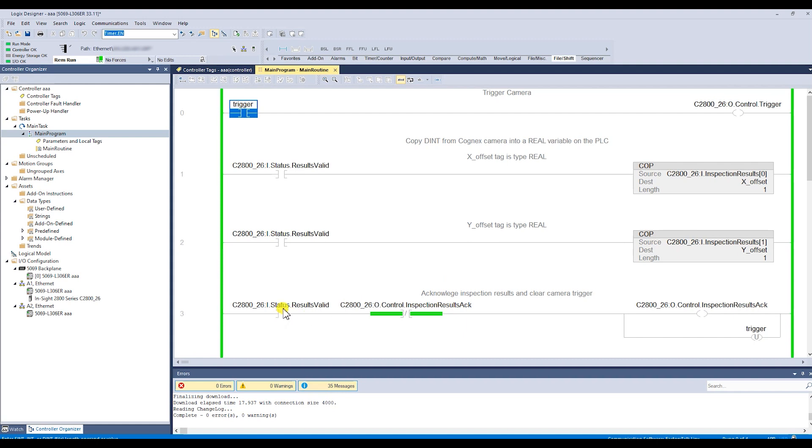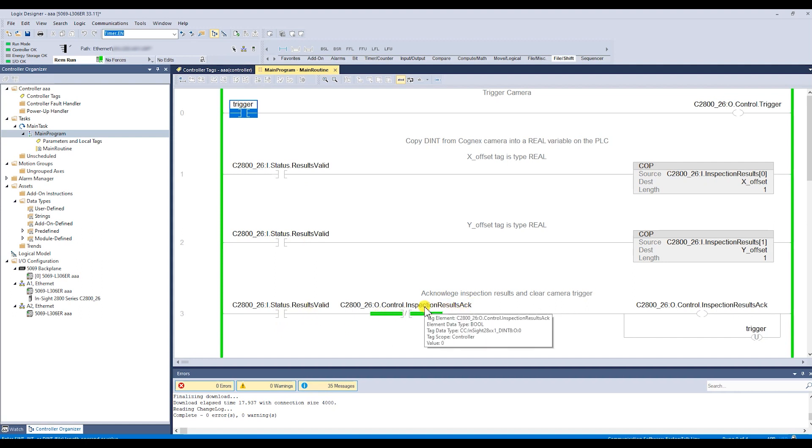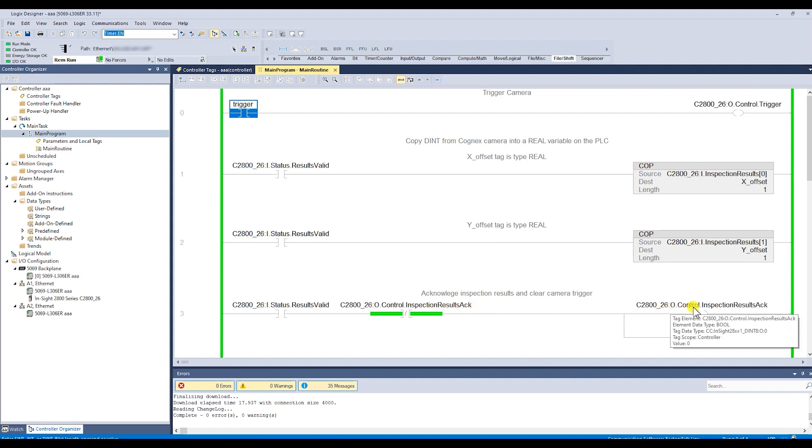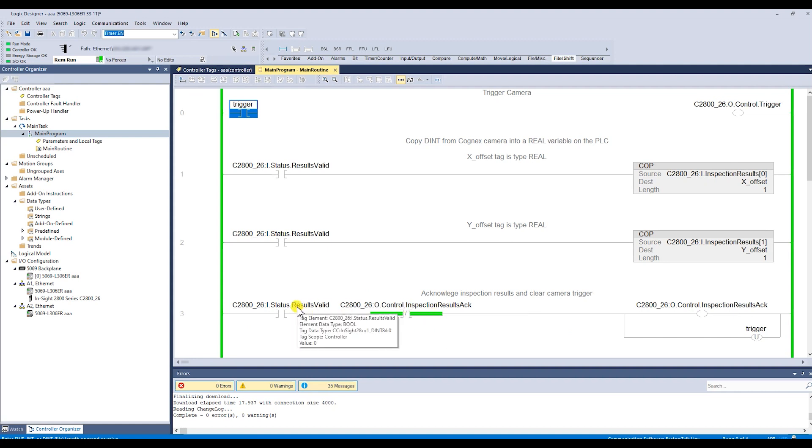Then the logic says that if the results are valid still, which they are, and the PLC is not acknowledged, then acknowledge it and then turn off the trigger so it's not still true. The way the PLC works is it scans from 0 to 3 and then goes back and starts over again. The next time it comes through, this is no longer true because results valid has been turned off and this is actually turned on, so that will turn that back off.